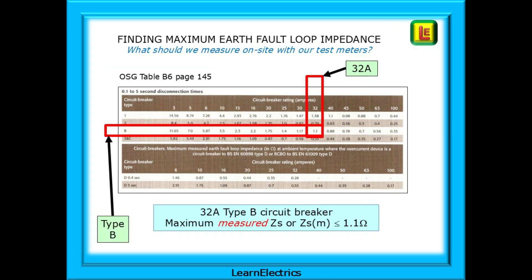The ZS value for different protective devices can be obtained from the On-Site Guide, Table B6 on page 145. For our example, find Type B on the left-hand side horizontal row, and the 32-amp vertical column along the top - where the row and column cross is our answer. ZS measured should not exceed 1.1 ohms. This maximum measured value has already been adjusted in the table for a C-min of 0.95 and a temperature adjustment of 80%, so there is nothing further for you to do to this 1.1 ohms.